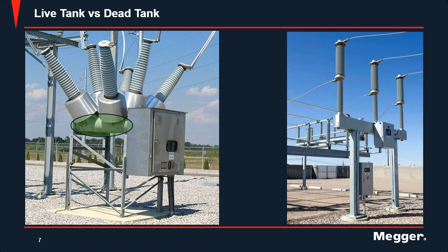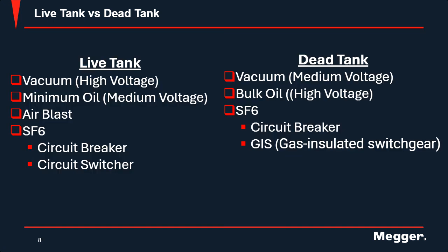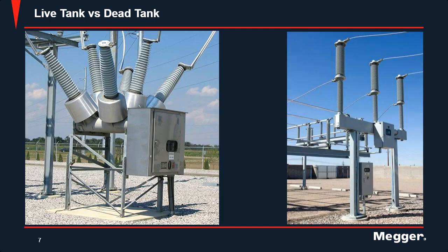When we talk about live tanks, as I said, the tank is live. So if you look up there at my little red dot, the interrupter inside of an insulation medium, that is live on the outside of that tank. It is not grounded. So that is just the basic understanding of what a live tank and dead tank is. Now, when it comes to different circuit breaker types, with live tank and dead tank, you have different breakers with different mediums for insulation material. So for live tanks, you can have vacuum breakers, so high voltage, minimum oil. If you remember on the last slide, what's red right there is going to be filled with either SF6 or oil. And if you look at the dead tank, obviously there's a lot more room for that medium.